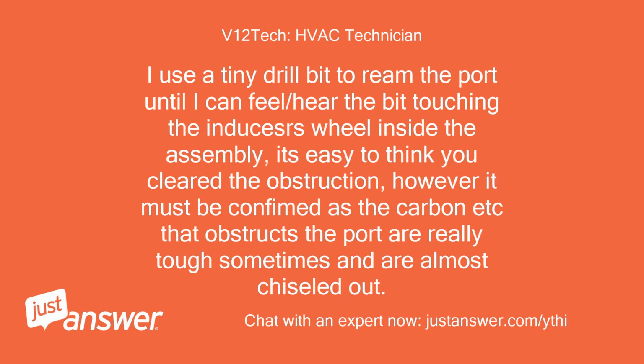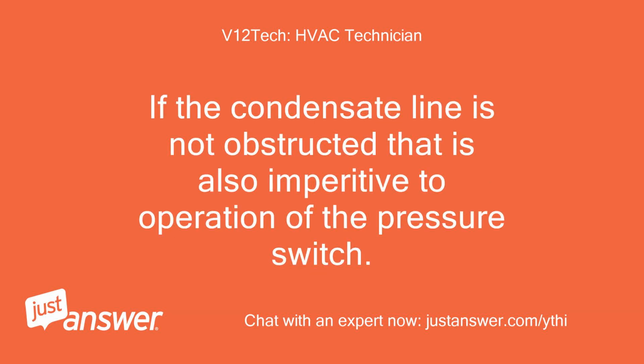I use a tiny drill bit to ream the port until I can feel/hear the bit touching the inducer's wheel inside the assembly. It's easy to think you cleared the obstruction; however, it must be confirmed, as the carbon etc. that obstructs the port is really tough sometimes and almost has to be chiseled out. If the condensate line is not obstructed, that is also imperative to operation of the pressure switch.